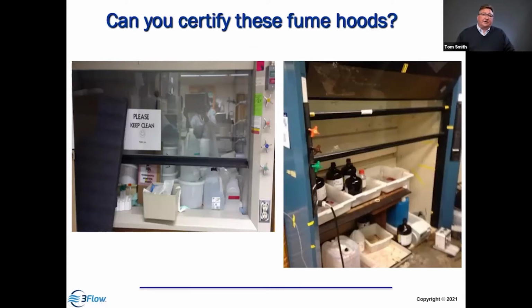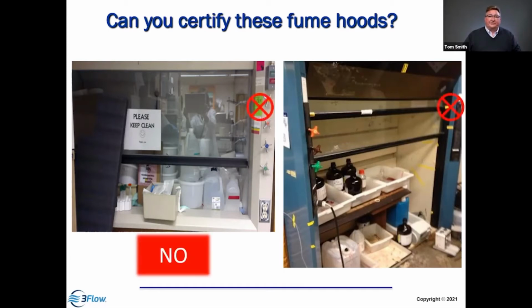Another case is you walk into a laboratory where there's all kinds of activity, and you go up to the hood and see something like on the left or the right. You can't even get in the hood, right? And there's a sign here that says, please keep clean. Well, apparently they missed the sign, because it's so loaded up with stuff you can't use the hood. And if we look at the hood on the right, it's got so much stuff in it you can't close the sashes. So the question is, can you really test these hoods? Can you verify they're functioning properly? And the answer is no, you can't.